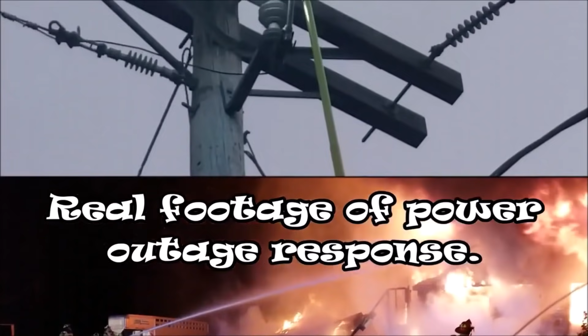First step, before we even go inside, is we've got to notify our dispatcher. Some companies may not have a dispatcher as part of their procedure, but you're out here in the middle of nowhere by yourself, somebody's got to know. A lot of this equipment is remotely operated. You don't want to be underneath an air breaker as it's being remotely operated. Those things are loud, they could fail, there could be compromised equipment in there. It's just a good idea for someone to know where you are. Pretty standard procedure, only takes a minute.